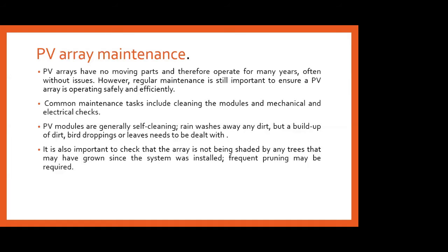And of course, not only cleaning the modules, we have to do the mechanical and electrical checks. Mechanical means checking whether any damage has happened to the structures for your PV arrays. And with respect to the wiring connections, those have to be checked often. It is recommended that PV modules are maintained only by suitably trained people, not by a common person. It is better to have all those things checked by a trained person. But for cleaning your PV modules, a trained person is not required. The customer themselves can clean the PV modules.